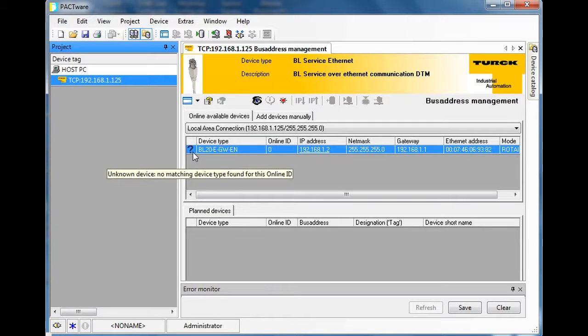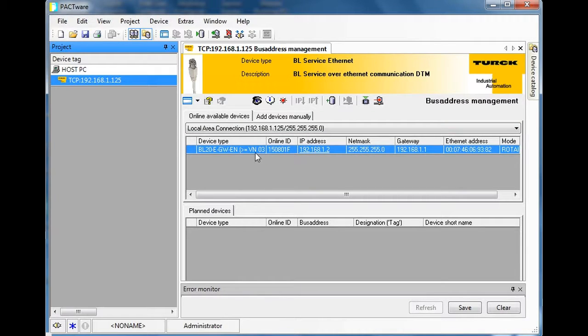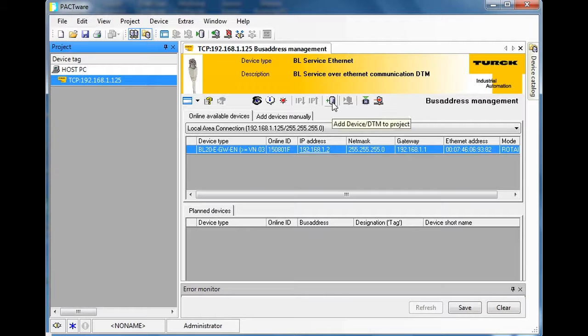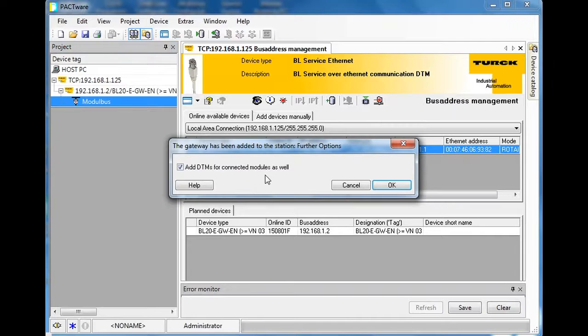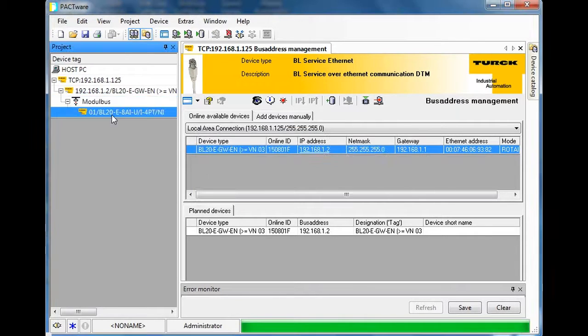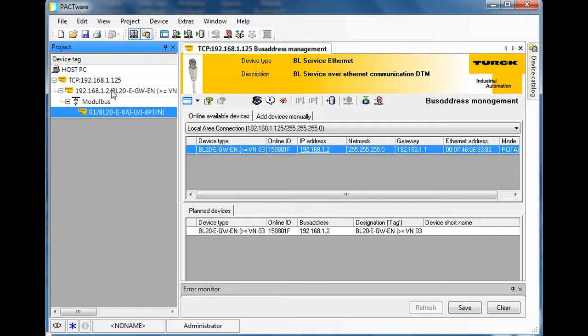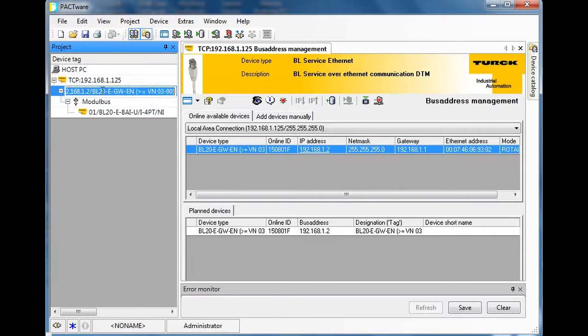Notice what it did — it went out and found the BL20 node but it says 'no matching ID.' When I scan a second time, it comes in and matches with the correct online ID, which matches the DTM file. This button right here will add the whole system to my rack, so I'll click on it. It asks if I want to add the DTMs — I'll say OK, and you can see on the left-hand side that it built my system.